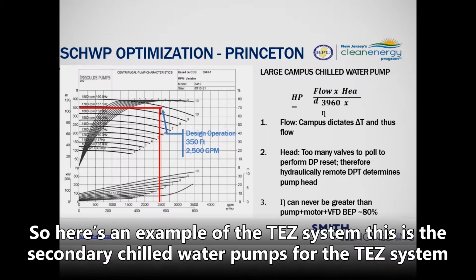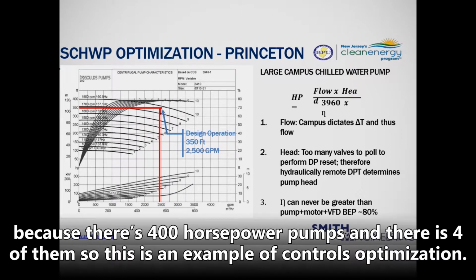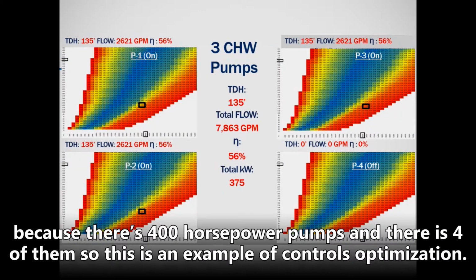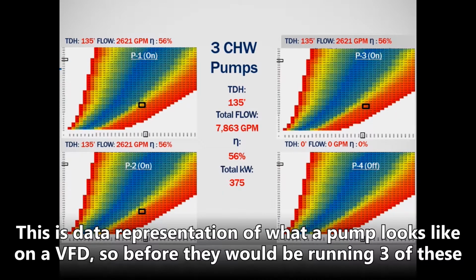So here's an example of the TES system. Secondary, my slides got messed up. So this is the secondary chilled water pumps for the TES system. These are 400 horsepower pumps. There's 4 of them. So this is an example of controls optimization. This is data representation of what a pump looks like on a VFD.